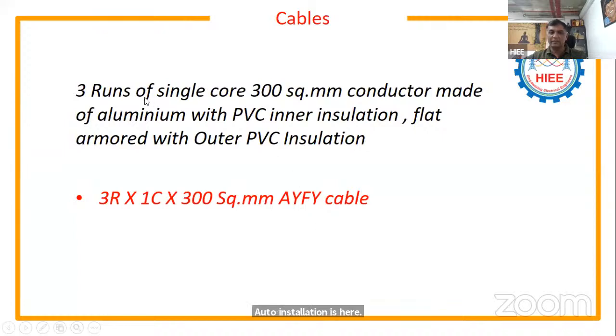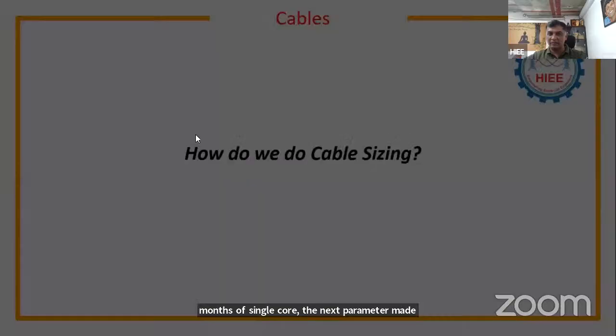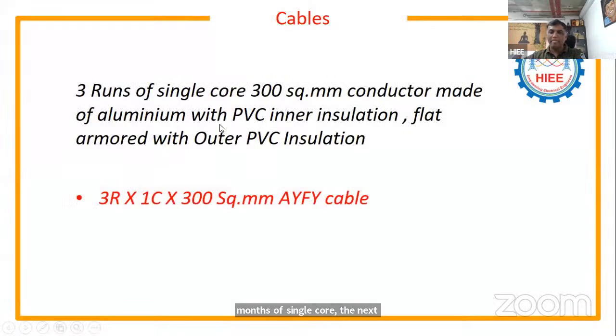Okay, here it is mentioned: 3 runs of single core 300 square mm conductor made of aluminum with PVC inner insulation, flat armored, and PVC outer insulation. This is how we give the nomenclature of the cable.